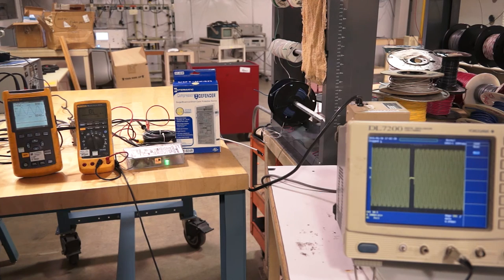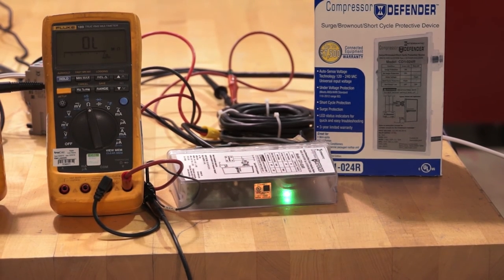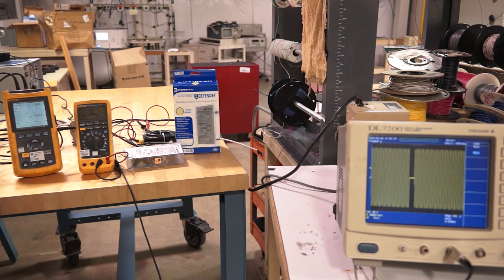The flashing state indicates the compressor defender has shut the central air conditioner system or heat pump down, protecting the equipment, and is now in a three minute short cycle delay mode.